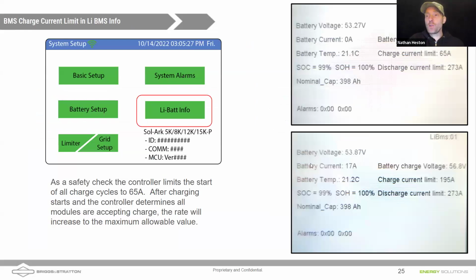If batteries are communicating properly, if you've got everything set up properly, you'll see a lithium battery info screen here. And if you check that, you'll see information like is appearing on the right side of the screen over here about the batteries, information on the batteries. So that extra menu appears in setup when you have communicating batteries. Also, it's worth noting that our batteries will request 65 amps. That's the value one battery can take until a charge cycle begins, and then that value will increase up to the global maximum that you set.